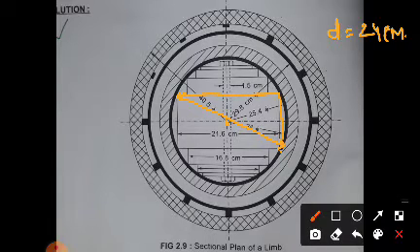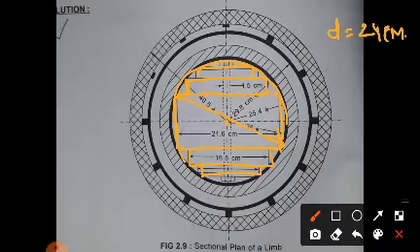This is the first step. L1 you know, and L2 you know, and L3 you are also going to get. This is very familiar, so you draw the 3-stepped core material. Then the internal diameter of the LT winding, the winding which is near to the core, is given as 25.4 centimeters. This black one is some insulating material, paper insulation or cotton insulation, provided on the core material.